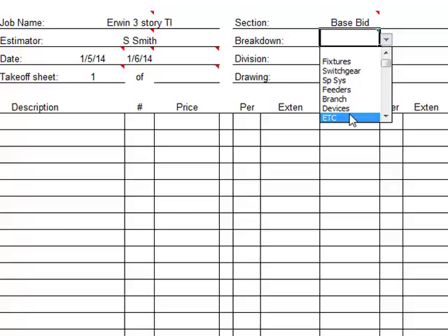I've had two really large projects where we actually put in, in one case, 6 generators. They cascaded as needed. This was in a hospital. Between the load shedding, switchgear, and the generators, it just behooved me to go ahead and break out the generators on their own, so I didn't put those under switchgear, which is how I would normally do it. This was an exception.